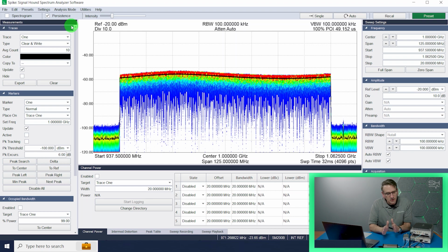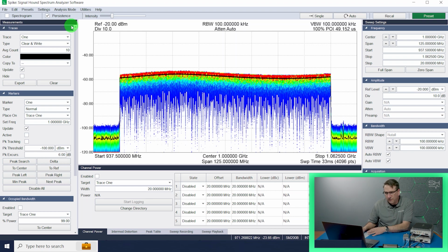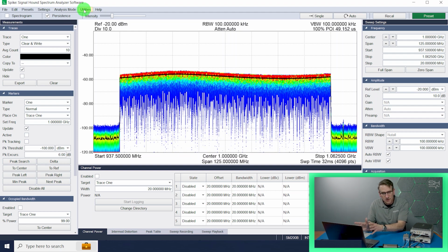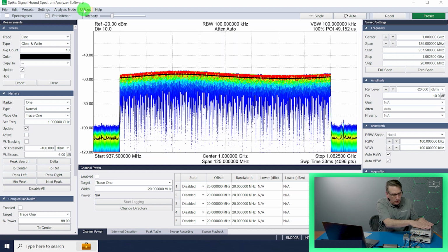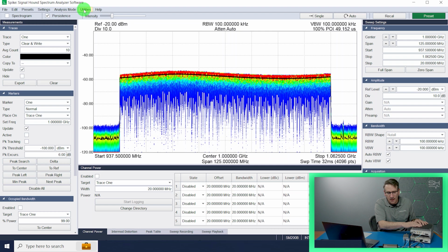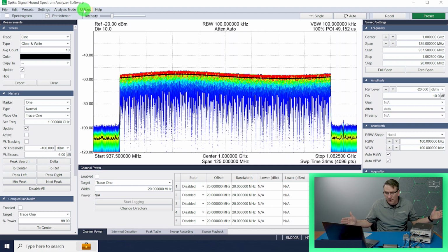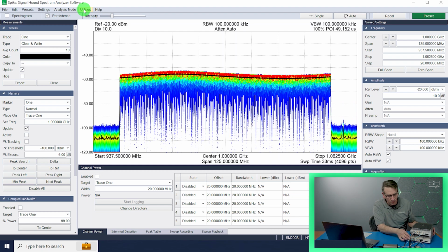So where does the difference actually matter? The difference actually matters anytime you need 160 megahertz or full bandwidth streaming. If you need full bandwidth streaming because you've written your own applications, well, then you would care. You would want to look at an SM200C model. If you were just taking measurements and you didn't mind that you were strapped 3 feet away from your PC, then an SM200B model might actually be the preferred model for you. You can save a little money with the SM200B model.